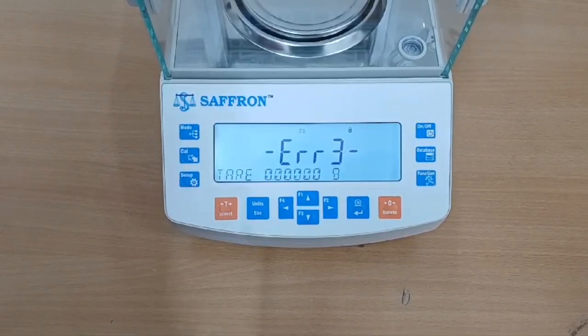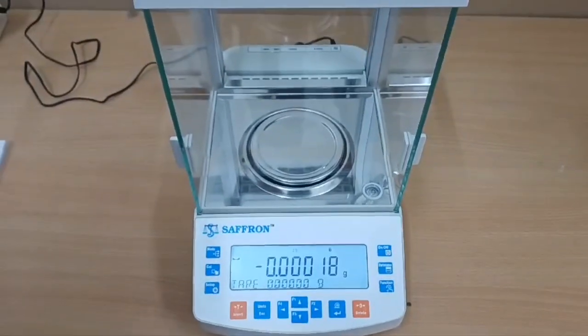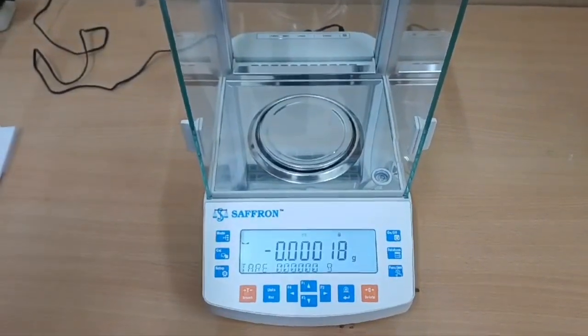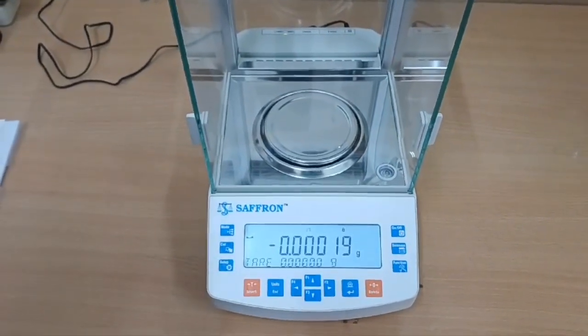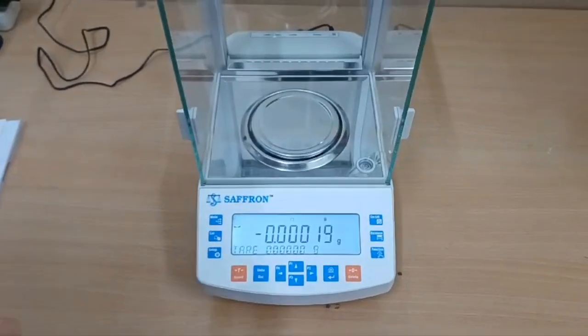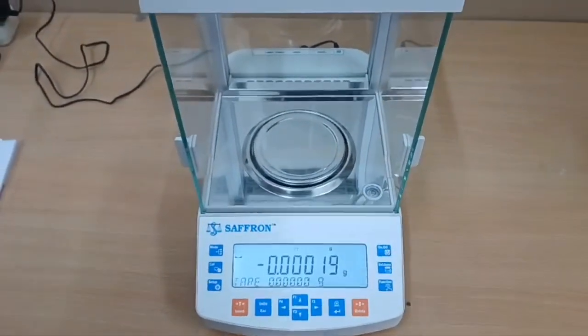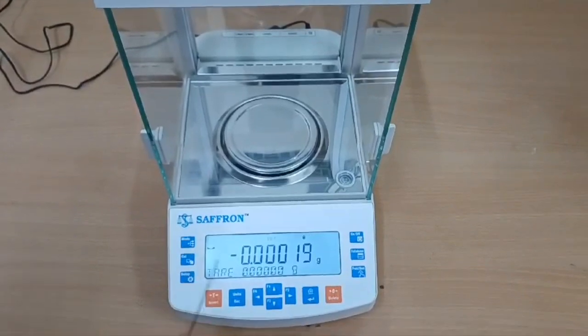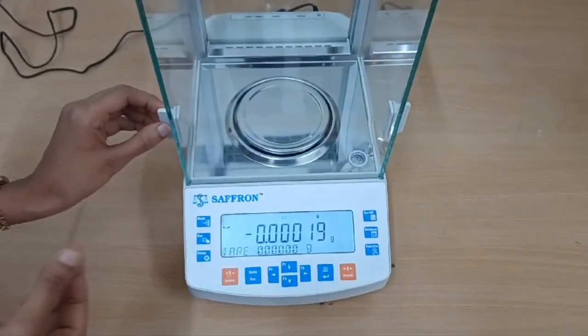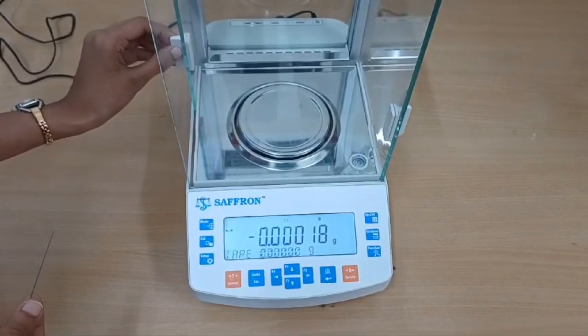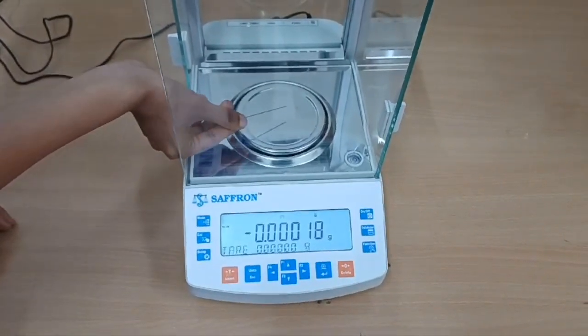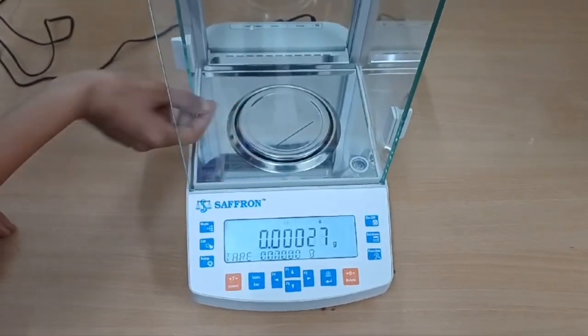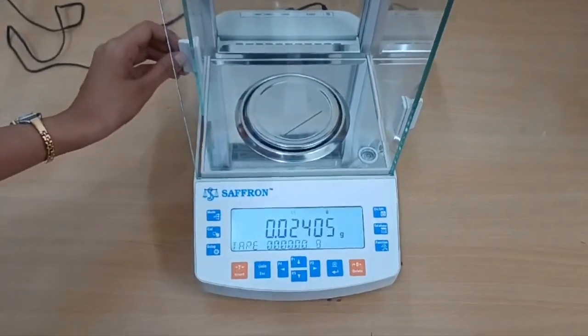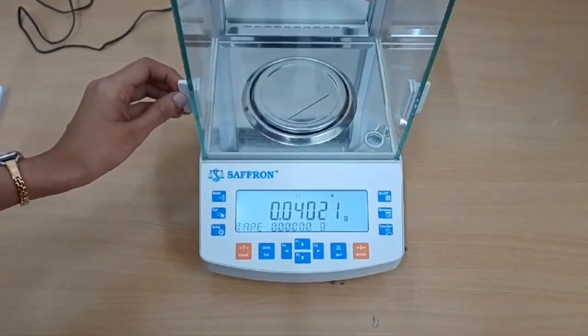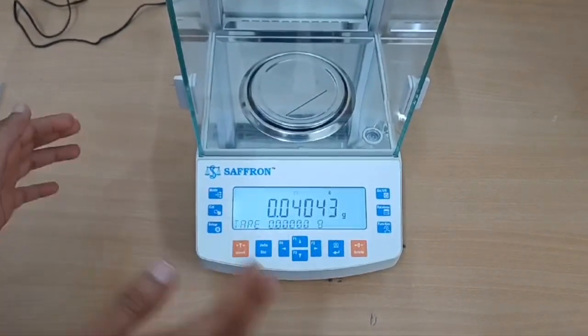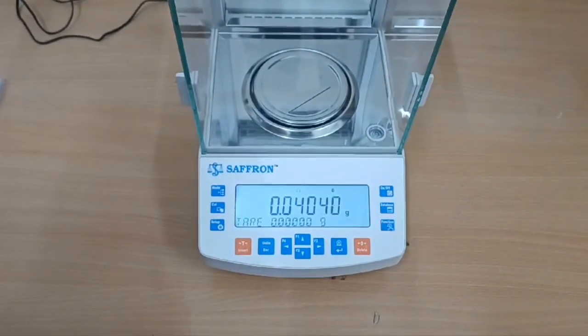Now it's showing an error because we're currently in an unstable environment and the vibrations affect the instrument since it's very sensitive. It's meant actually for a laboratory environment where there are no disturbances. Just for the procedure, we'll now demonstrate a pencil lead being weighed. The specimen must be carefully placed on the weighing balance. And the door must be closed before the reading is taken to ensure that there are no vibrations and external factors affecting the measurement.